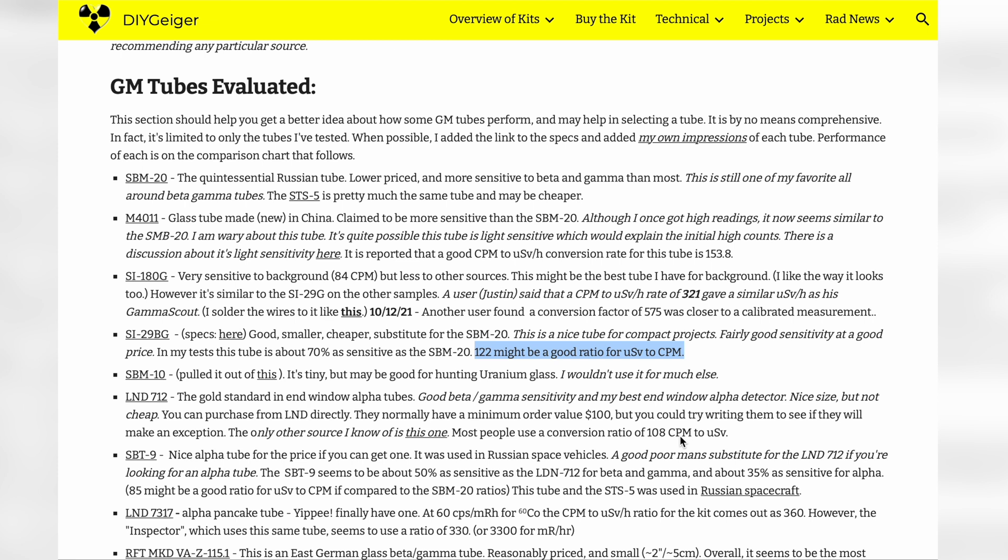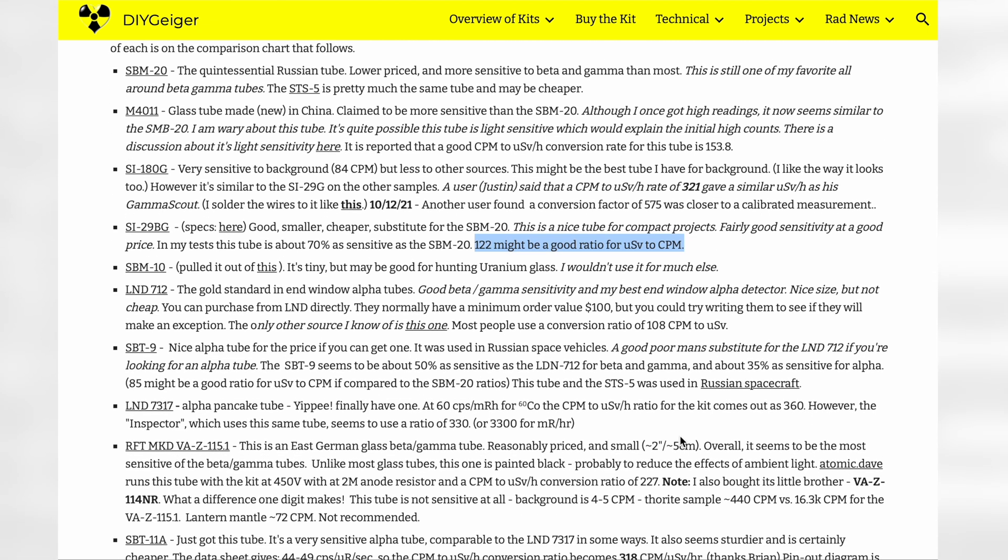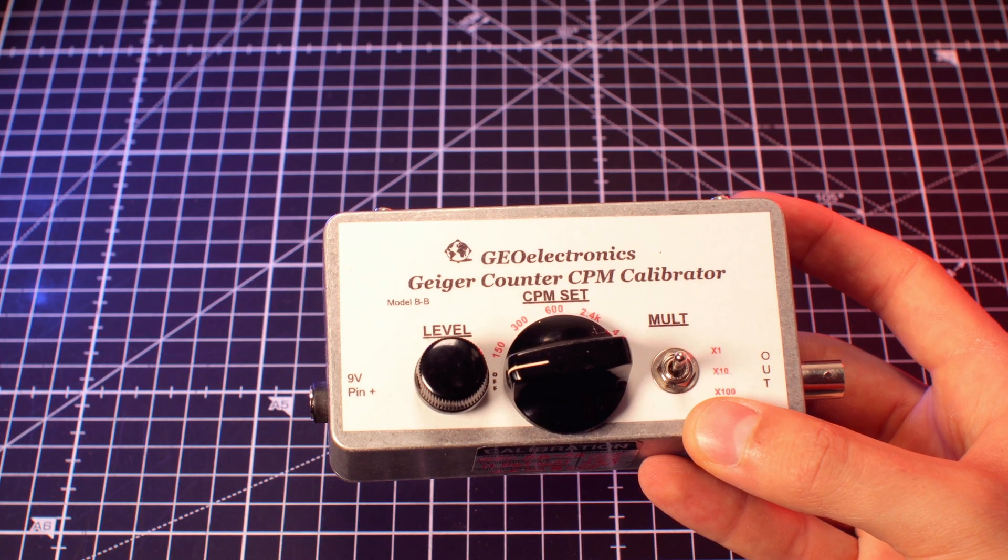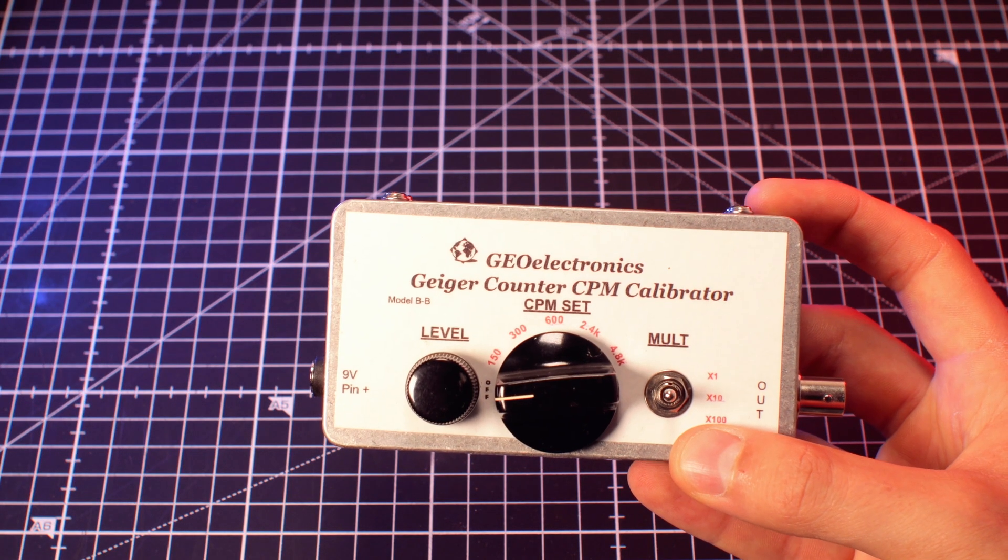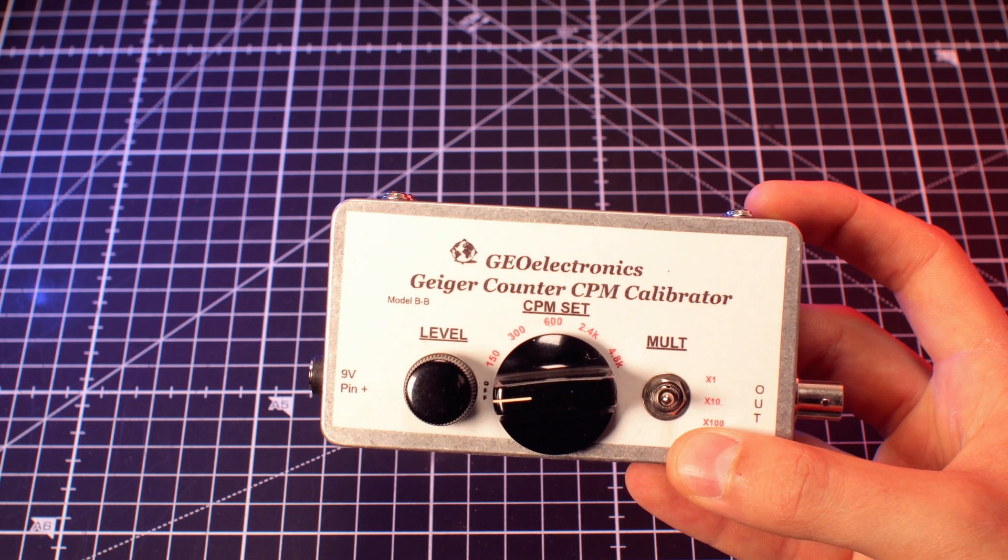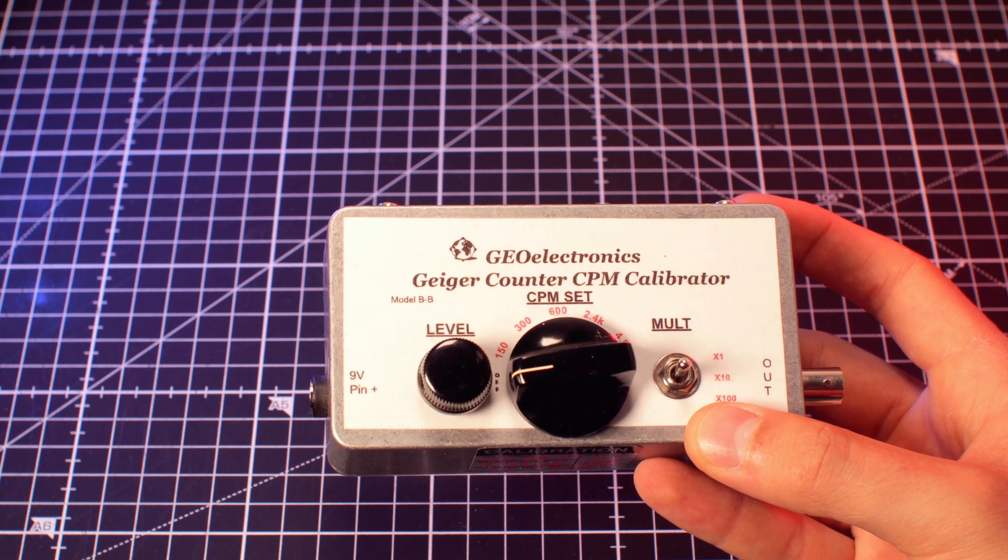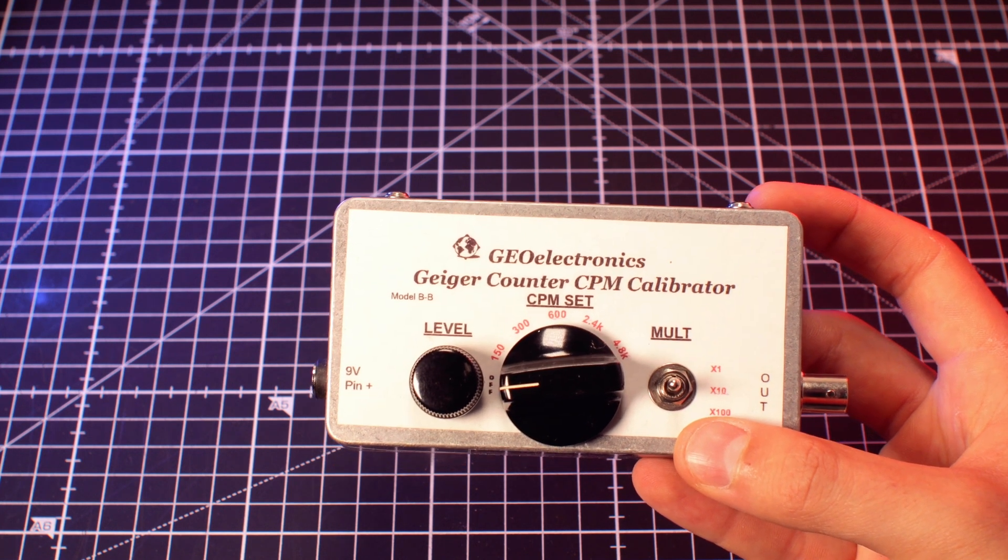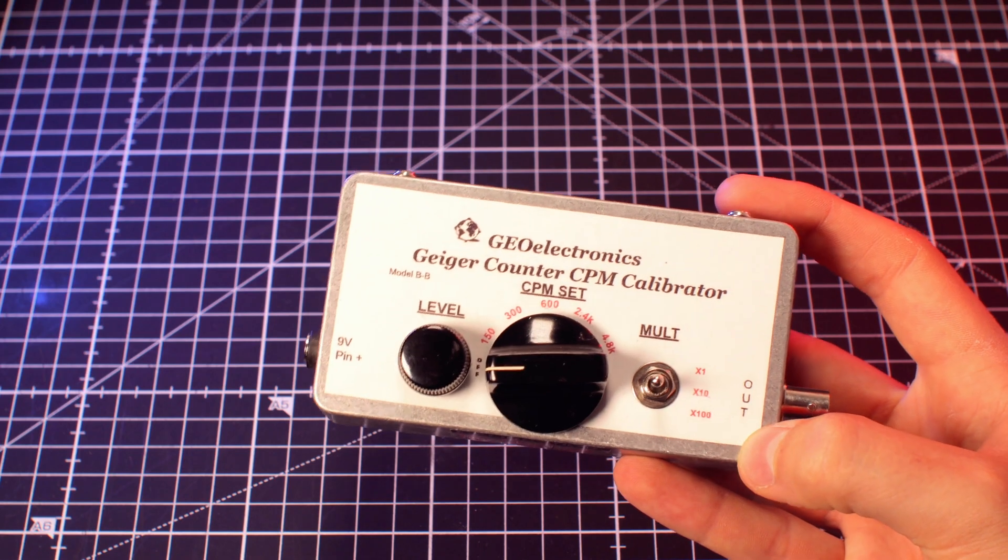Please note that this isn't very accurate and if possible you should use CPM when measuring the activity of samples. Those units work only when the meter is calibrated to the specific isotope which is being measured. In other cases, the readings can be lower or higher than in reality.